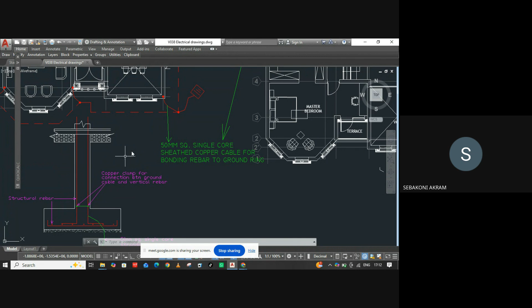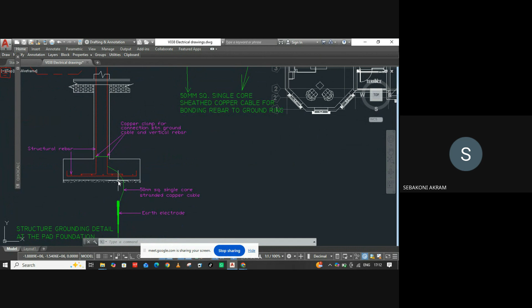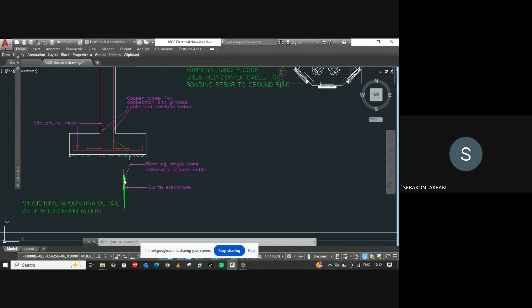So we bond a copper cable to those rebars, then we connect it to the ground ring that we've formed. So that ground ring is then connected. You see this schematic here. So this is the bonding to the rebar. Then from that rebar, we connect to the earth rod. This earth rod is the one really connecting to the ground.